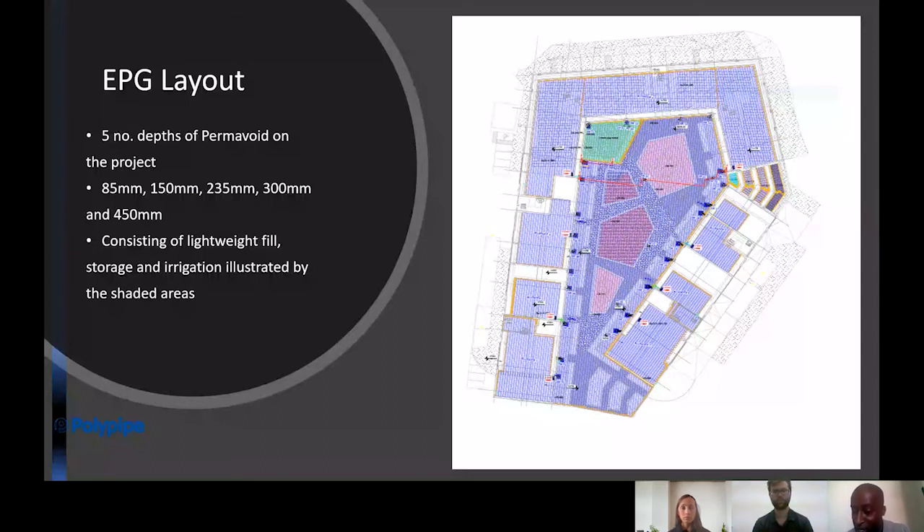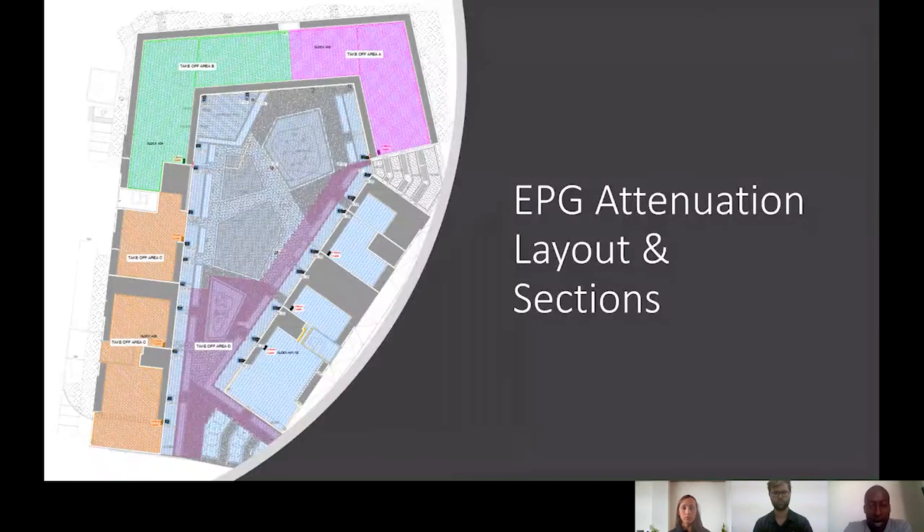Only at the point when we've extracted as much as we possibly can from the natural asset is the water then discharged into the sewer system. On this project we had various depths of permavoid: 85mm units on the roof; and depths of 150mm, 235mm, and 300mm and 450mm on the podium. These consisted of either lightweight fill within those units, passive irrigation, or pure attenuation — three different solutions within the system, designed by EPG.